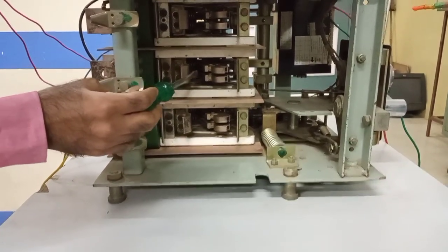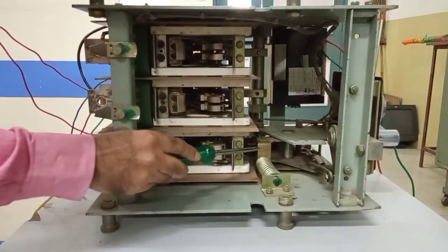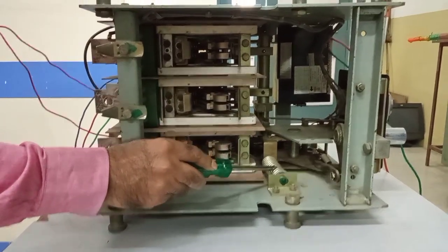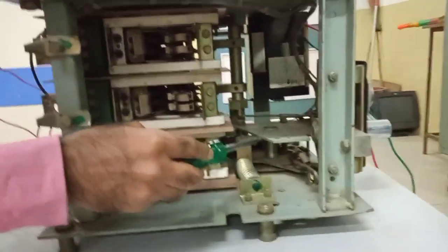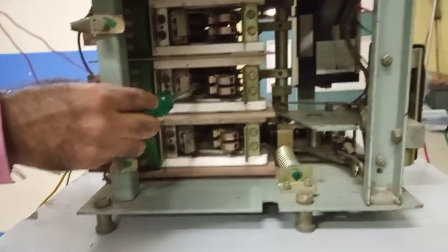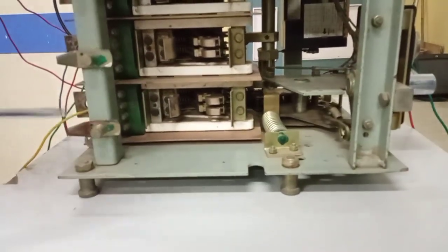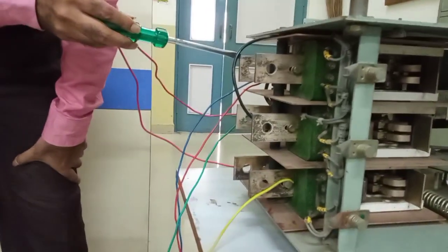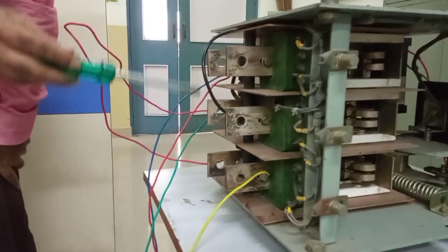Now besides the main contact and arcing contact, we have here the operating mechanism, which is the spring. Here you can see the spring operated mechanism, and then various mechanical linkages are there. Through these mechanical linkages the signal is given to these contacts so as to activate the contact from open position to the closed position. Now on this side you can see the incoming and outgoing terminals. This is the incoming and outgoing terminal for R pole. Similarly this is for Y pole and this is for B pole.